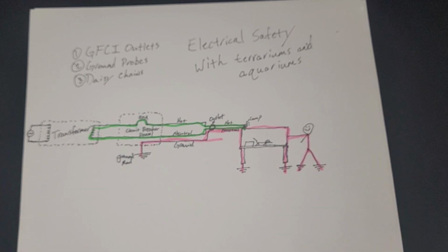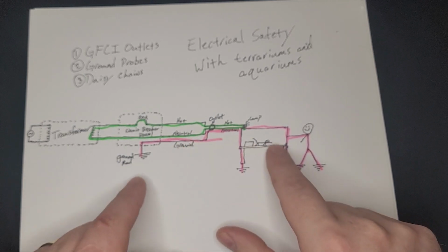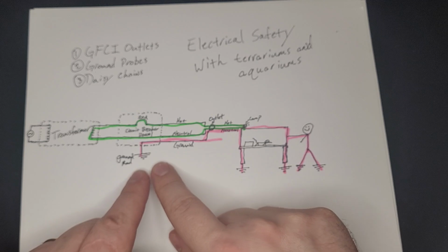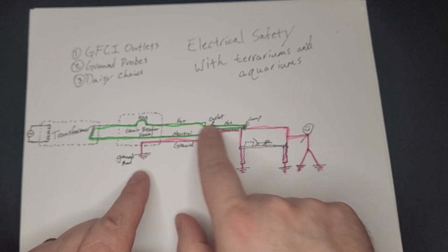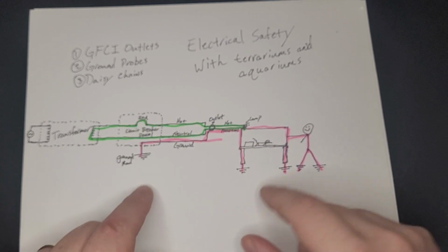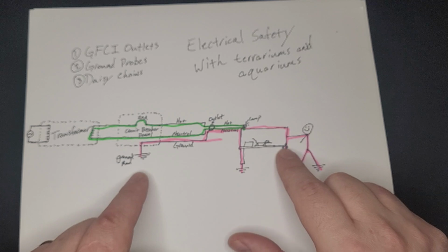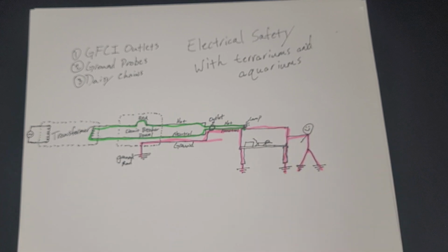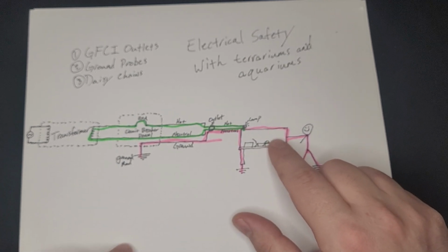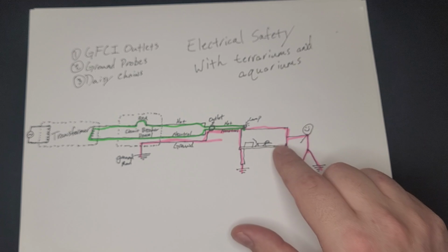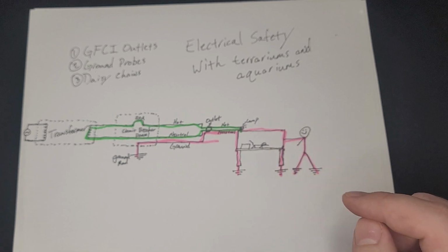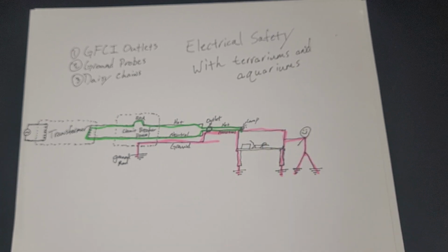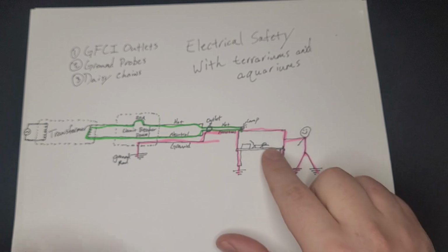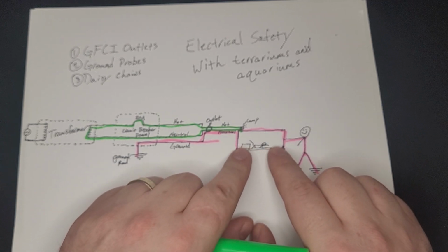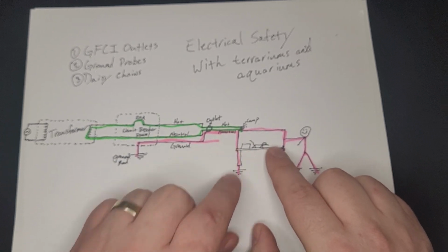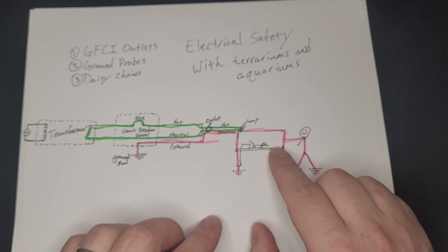So in my opinion, it's better to have the ground wire and allow that current to flow there, even if it potentially trips other breakers, whether it's the 20 amp breaker or the GFCI. It's better to let that happen than to have a charge building up waiting to surprise you when you touch it. I'd rather have it trip some sort of issue. The other thing is, you really shouldn't have a charge building up there, and that's a sign something is wrong with one of the appliances.